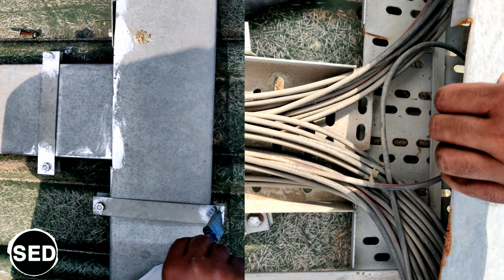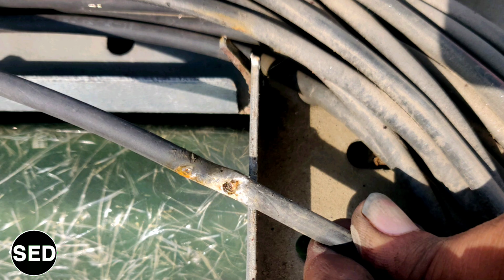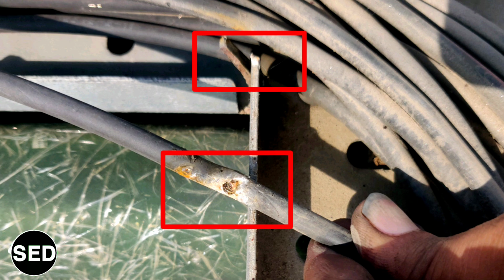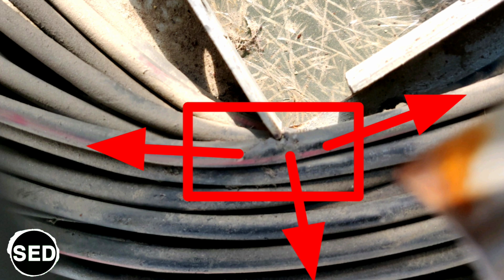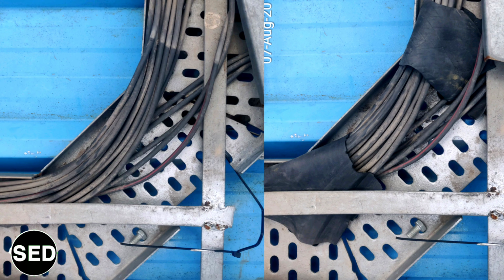There are very high chances that if you have a T-shaped cable tray, the cable is likely to get tampered due to the sharp edges at the turn, and permanently damaged due to lateral contraction or expansion in the cable during operation at different temperatures.